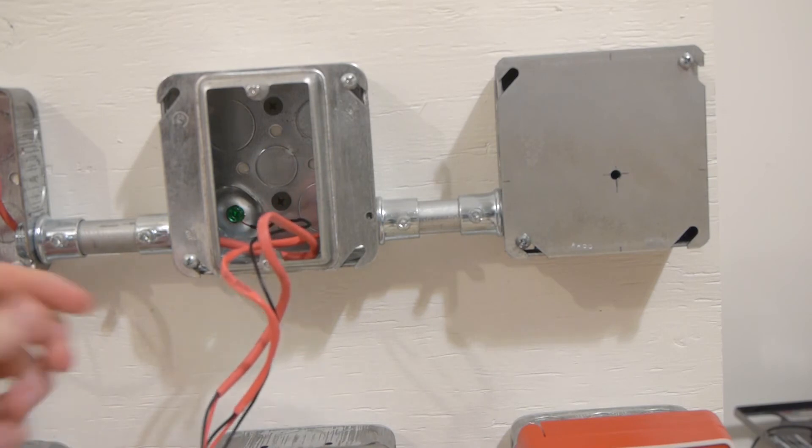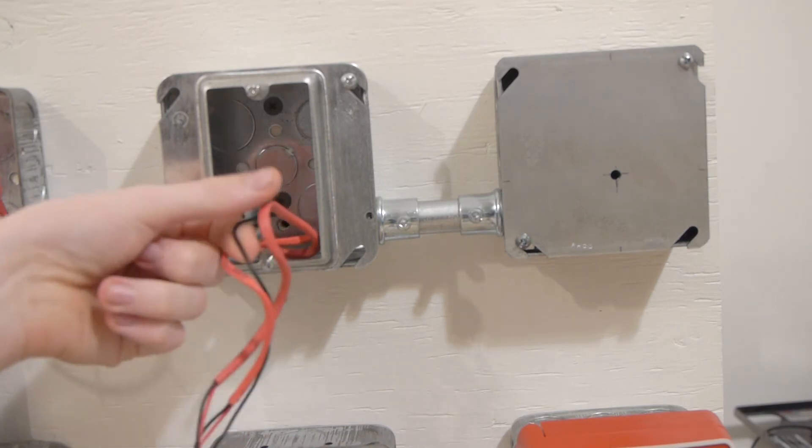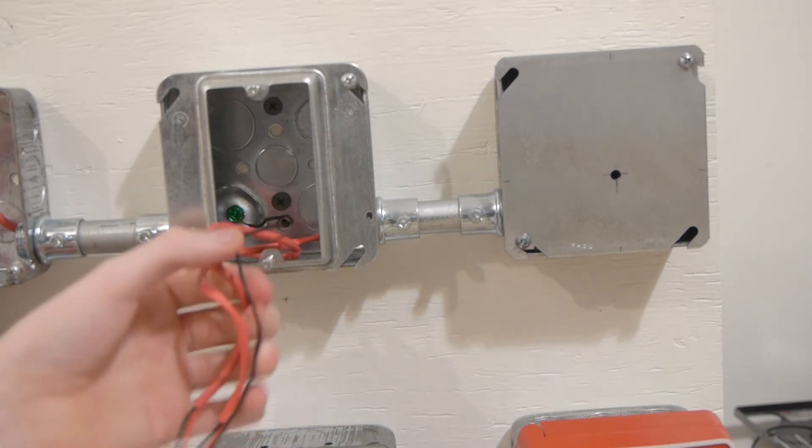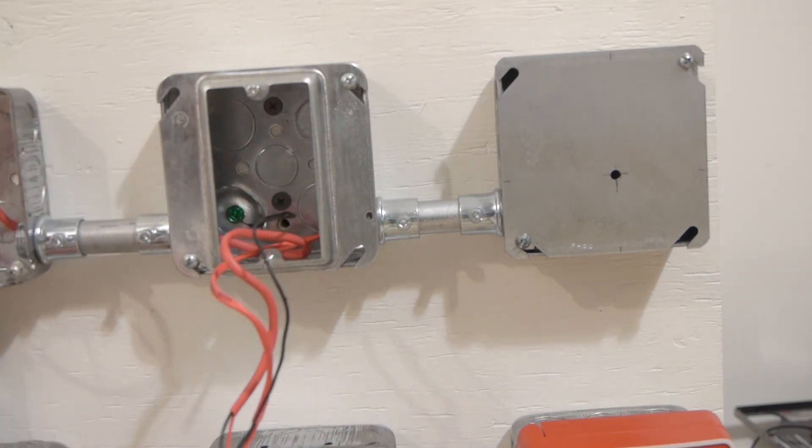Now once I pull it off, as you can see there's our ground fault, which I just put a wire here. Normally it would be a chafed wire or something like that, but I just put a wire here just so it wouldn't go away while we were troubleshooting.